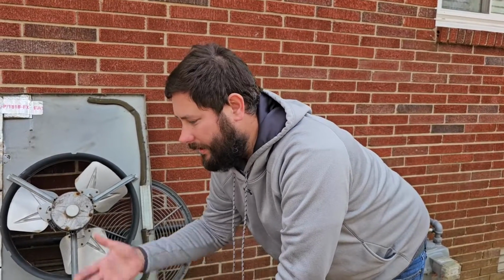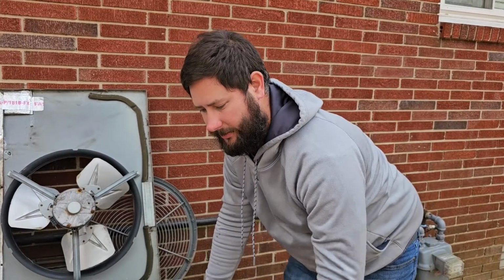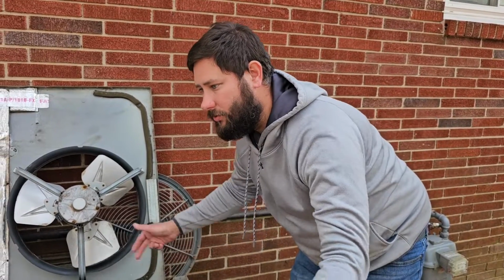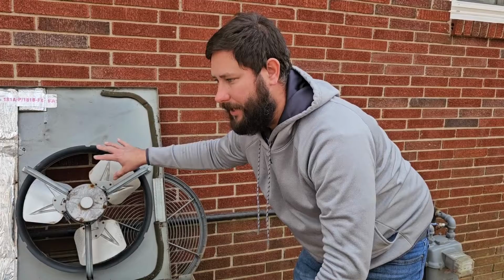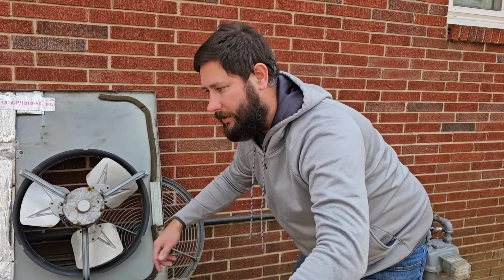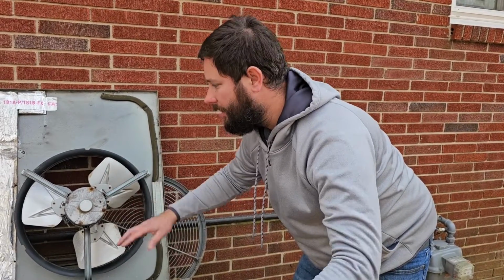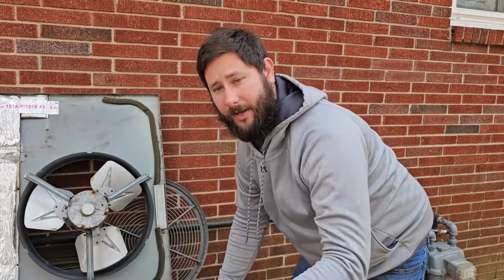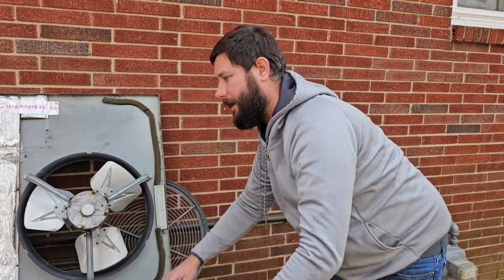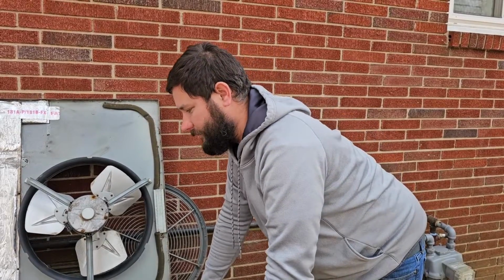Got a call from the customer. The customer is very concerned about carbon monoxide poisoning, so they wanted me to inspect the heat exchanger. To get to the heat exchanger for this style unit, you're going to take off all of the screws that are connecting the top panel to this unit. Once you get those screws out of the top panel, you can just fold that panel back. It's easy when you have two people, but you can do it yourself if it's just you.